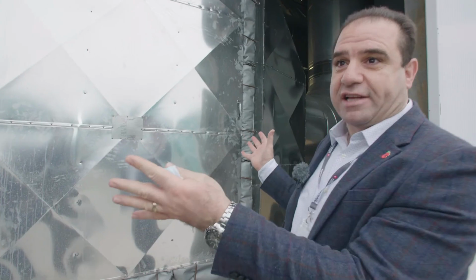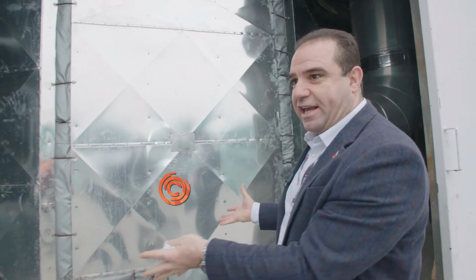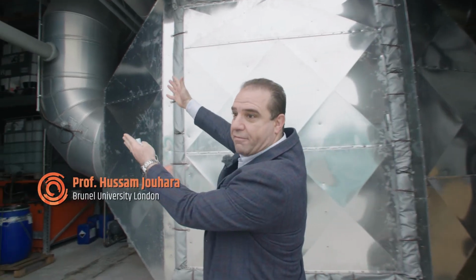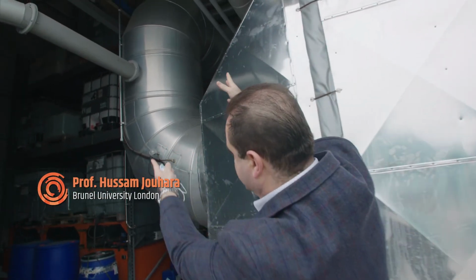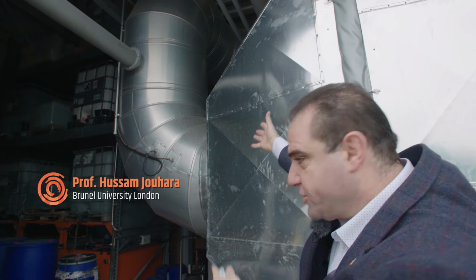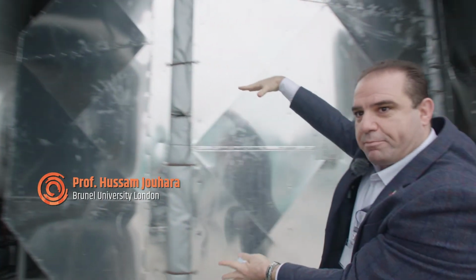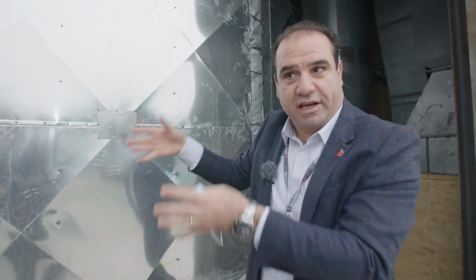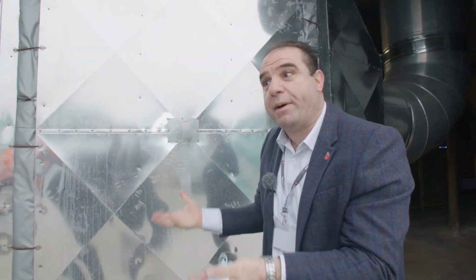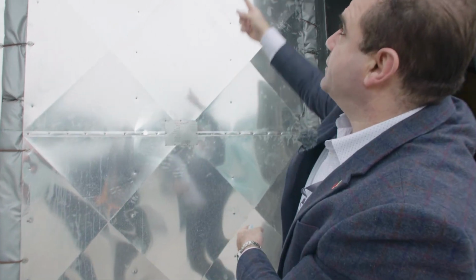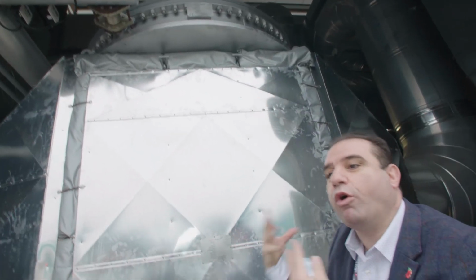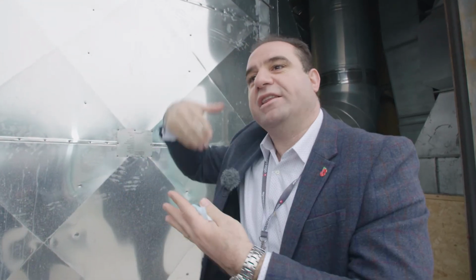The project aims at extracting heat in a passive manner from an exhaust flow coming through this duct from the process inside the factory. The exhaust goes through the heat pipe heat exchanger. Inside, heat pipes are staggered in a certain configuration to absorb the heat passively. The heat is then delivered to the shell, which heats a water flow to high temperature that goes to the factory to be used in various areas.